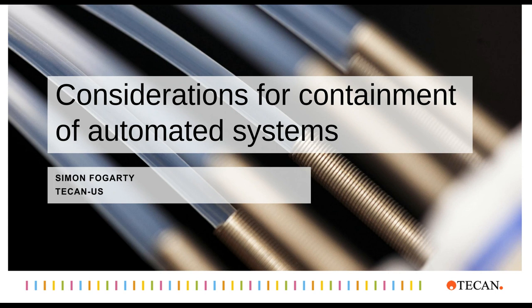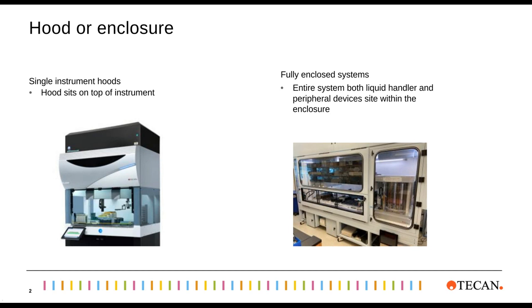What I'd like to do is do a short presentation first before David takes the floor, and talk about some of the main considerations for containment of automated liquid handlers. So, firstly, when you're looking at containment, you as an instrument owner have two real options. Firstly, you can have a simple hood that sits on top of the instrument. These can be connected directly to in-house exhaust, or come incorporated with simple HEPA or charcoal filters, depending on whether you're dealing with biologics or chemicals, and can provide filtration of the air after it's been handled from the instrument, either blowing air down onto the work surface for a clean air or an extraction-based system.